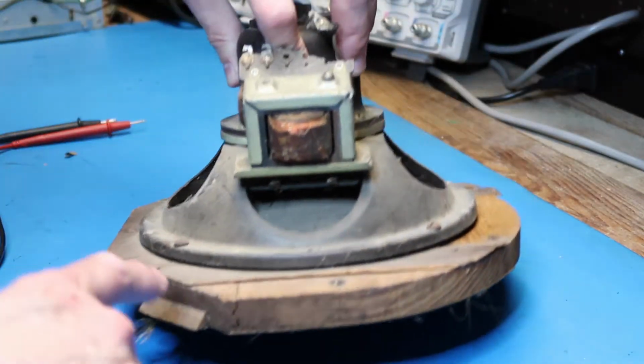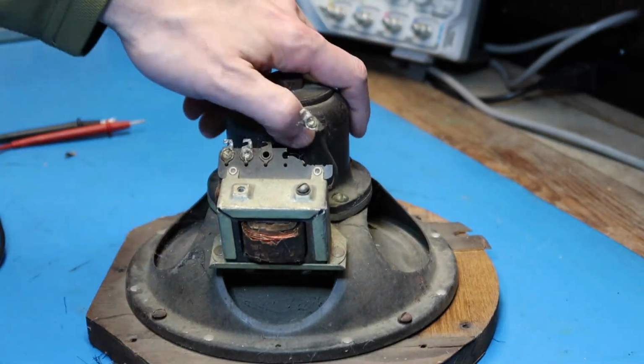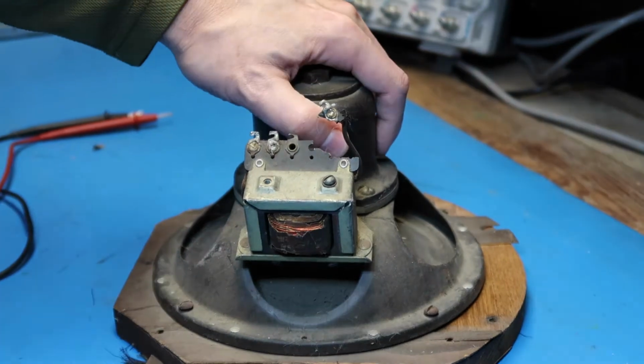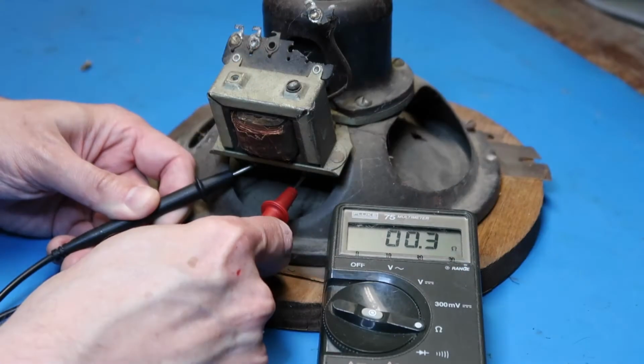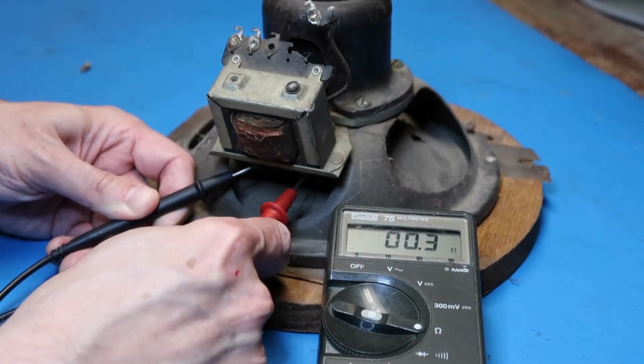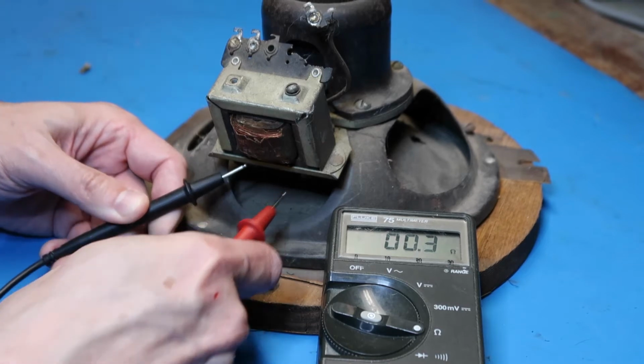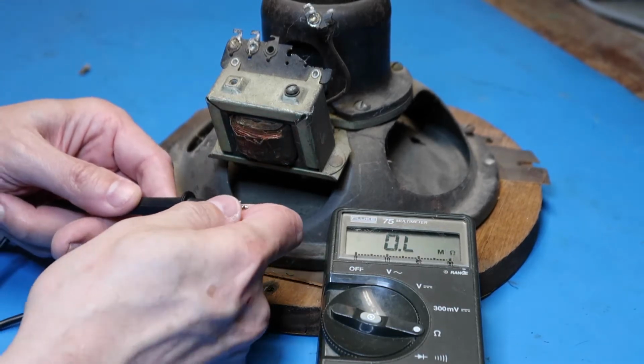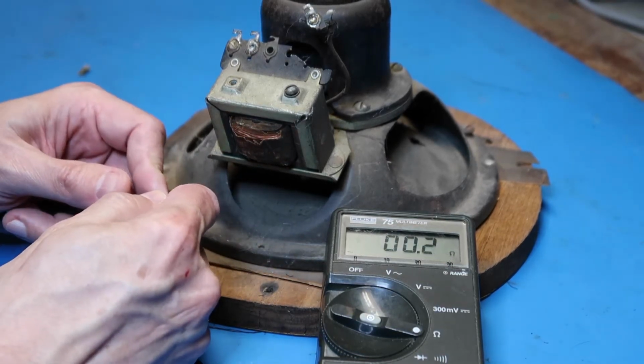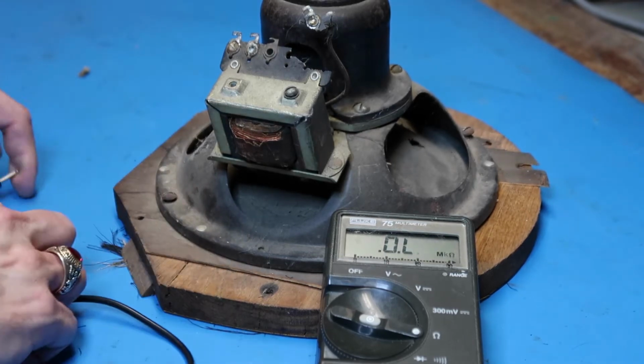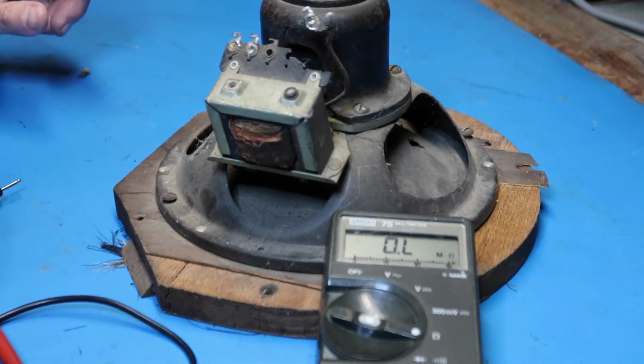Now we can reach these on the bottom. It's reading about 0.3 ohms - essentially that's a dead short. Let's short the leads together and see what we get - 0.1. So that's not good.